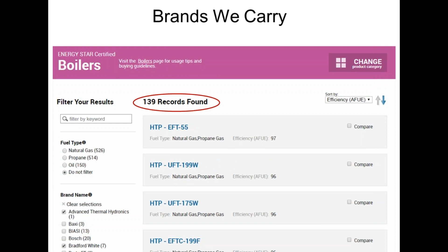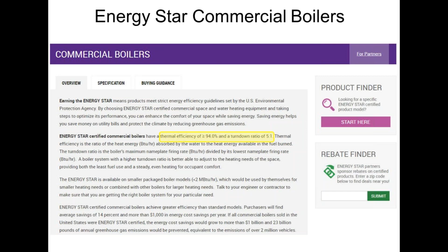Commercially, the spec is slightly different. A commercial sized boiler has to be 94% thermal efficient. So a residential boiler has to be 90% AFUE. A commercial boiler has to be 94% TE, thermal efficiency. Additionally, it has to have a 5-to-1 turn-down ratio, which is just a fancy way of saying it can modulate from 100% down to 20%. So it can't be like a two-stage 50-100 deal. It's got to be all the way down to 20% firing rate, a 5-to-1 turn-down ratio. Those are the two things it has to do.